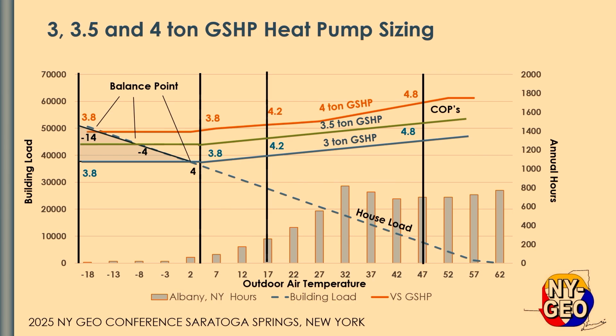Now this is outdoor air temperature, and so there's a corresponding loop temperature, but I didn't bother to put the loop temperatures on here. But this is a typical loop profile of, I think we hit a minimum of 32 down here, and it probably goes up to 56 maybe at the super part load. So your loop temperature's ranging in there. So you've got a 4.8 here, 4.2 at 17, and we've got 3.8 COP down at 5.